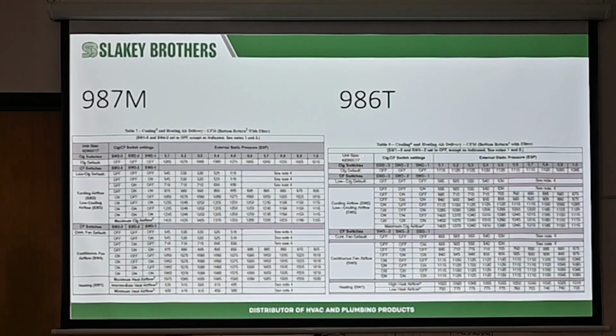Pretty much exactly the same over here in the 986. But the dip switch is configured for a different airflow depending on your static. So just because, in a perfect world, we try to design stuff for half an inch of static. These numbers, when we're trying to design for half an inch of static, you got to remember, that usually means it's a furnace only. Anytime you put a coil on top of that air conditioner, you got more static that is going to be added automatically. Automatically, you cannot get away from it.